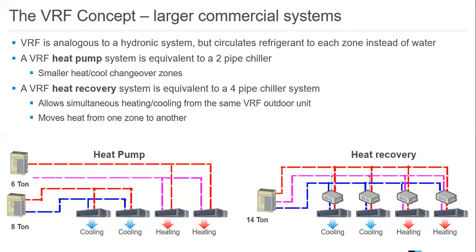It operates a lot like a 4-pipe chilled water system, where we can have simultaneous heating and cooling. In a 4-pipe chilled water system, that heating comes from a boiler, and we have 2 different coils inside of the indoor unit. But with VRF, we have a BS box. It's going to allow us to have that indoor unit switch over from heating to cooling and provide hot gas or subcooled liquid as needed.